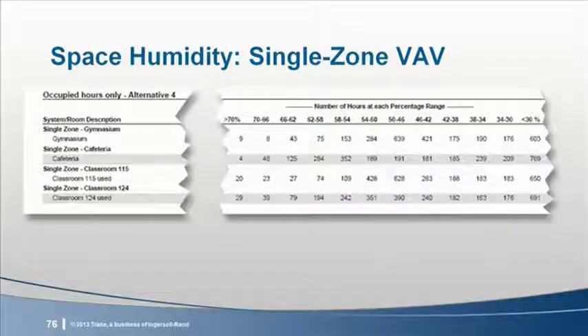Next, let's look at the same table for the SingleZone VAV system. Based upon the part load dehumidification aspect of a VAV system, we should see lower relative humidity numbers. Looking at the center section, where the number of hours for 5% bins are reported, we can see a significant change. There are fewer occupied hours with high relative humidity values, say greater than 62%. This should translate into a more comfortable space for the occupants and a reduced likelihood of microbial growth. The Building Humidity Profiles report is a convenient way to review the space relative humidity from the simulation.